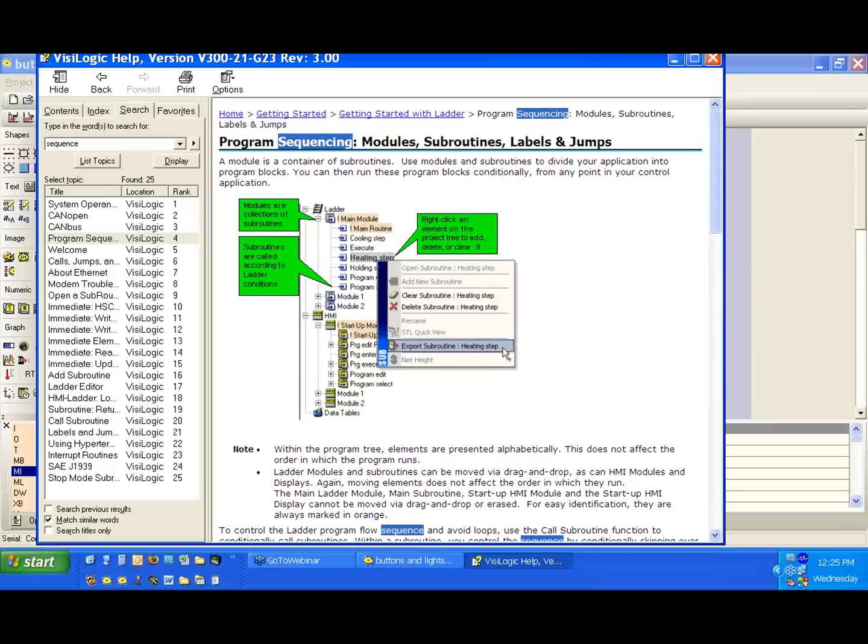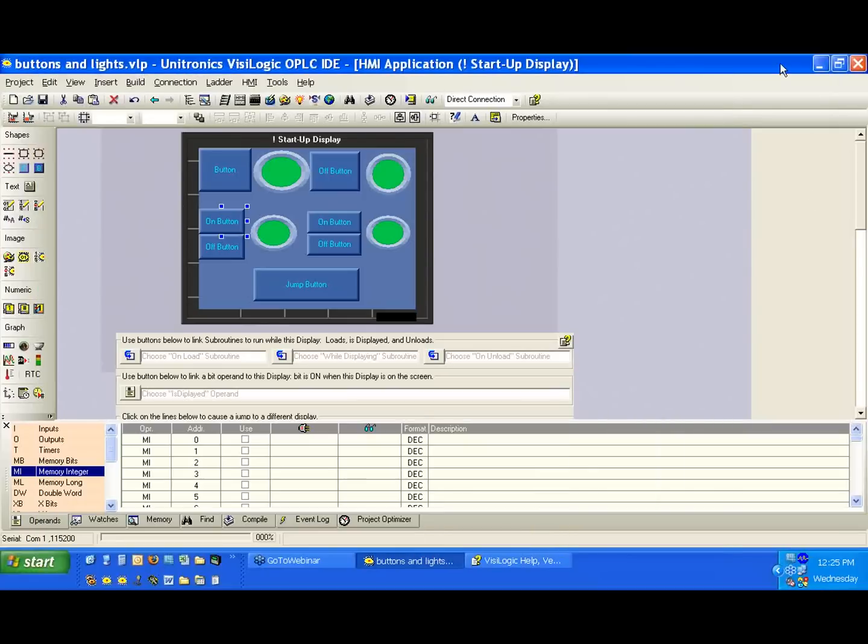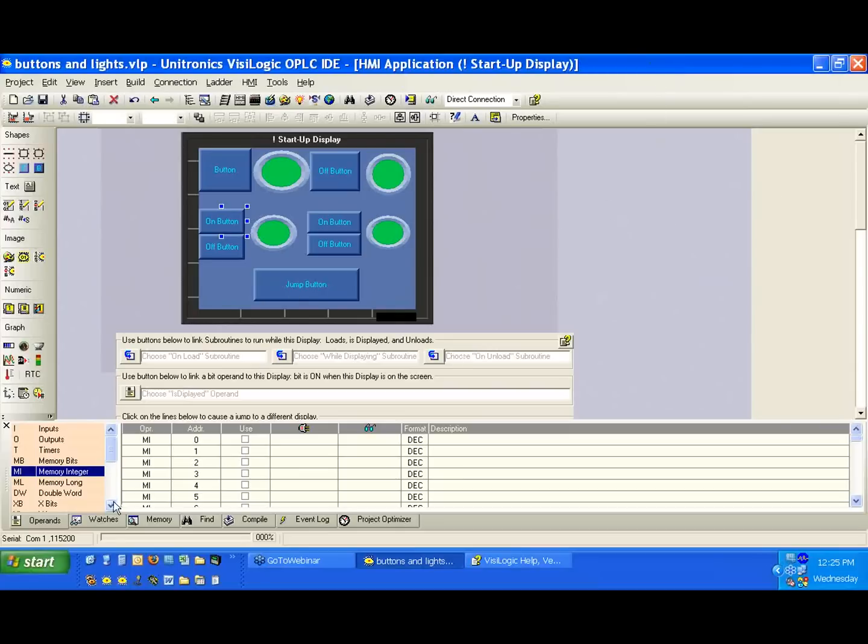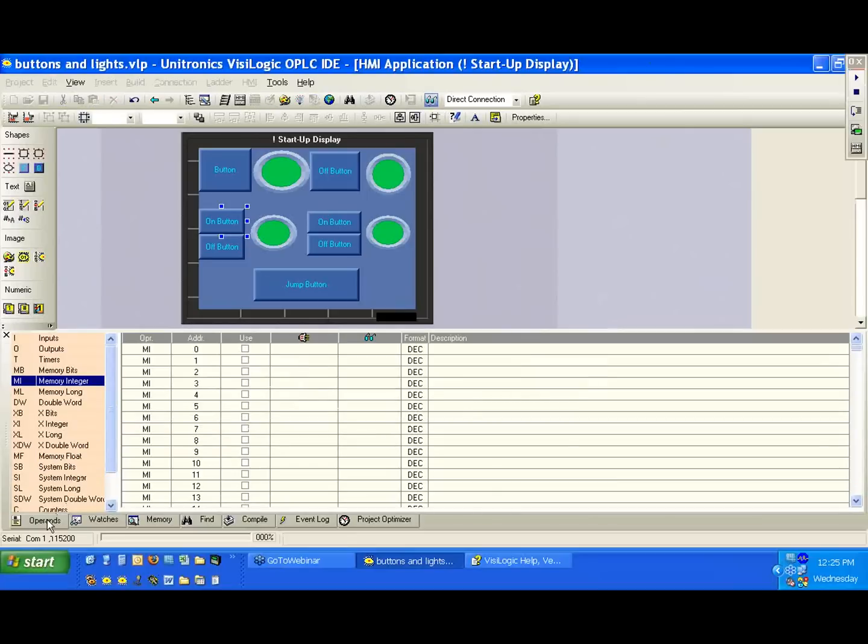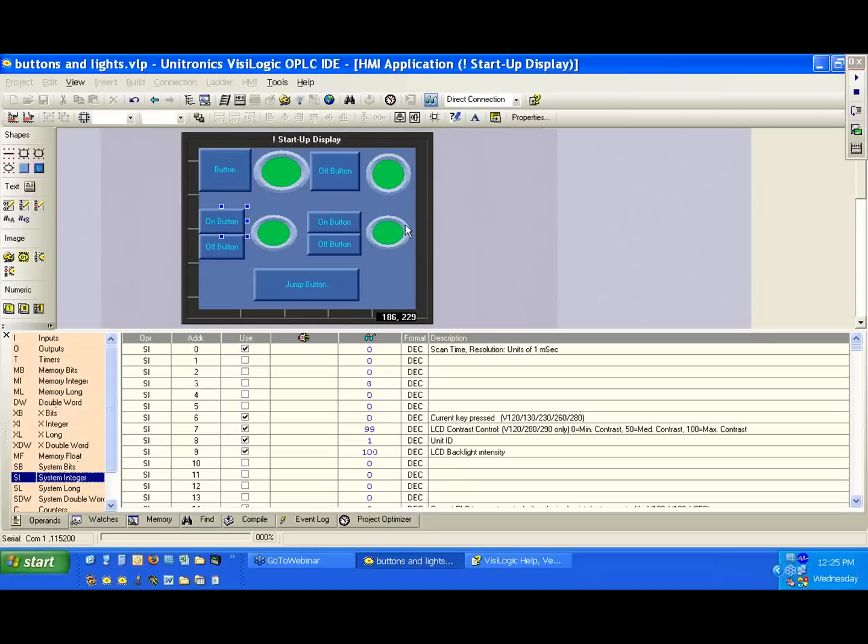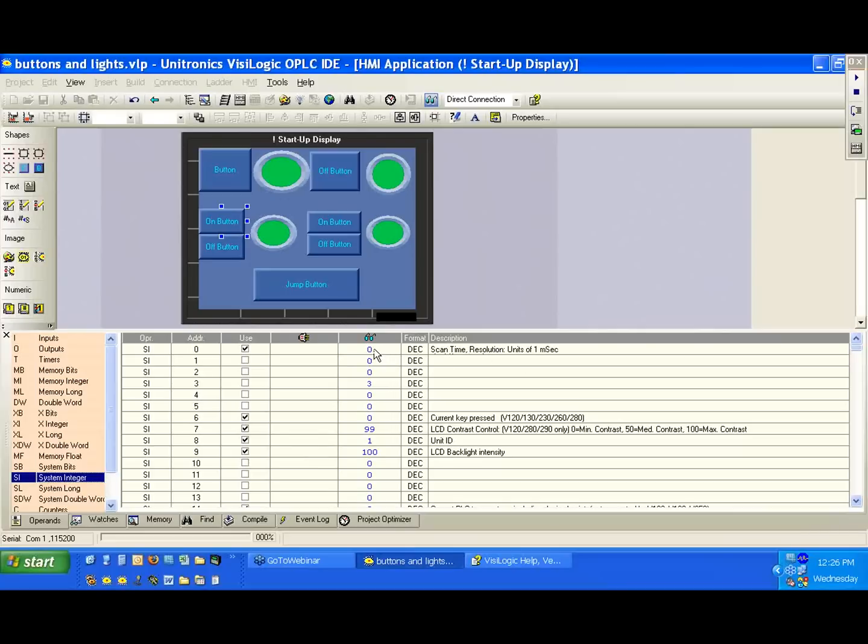There's a question, does the integration of the HMI allow for much quicker screen update times? I can say compared to a system where you have to set up communication and maybe Modbus tags, the answer to that would be probably yes. It takes between one and eight scans in general to update the HMI. And an example of a program scan time, if you want to take a look at the 570 we're working with right now, we can look at the system integer here, system integer zero. I'm in the online mode again, and I can view all of the values of the registers. Now, system integer zero holds the current scan time. It's obviously not zero, but it's less than one millisecond. So the update time to update our HMI is probably one to two milliseconds in this case.